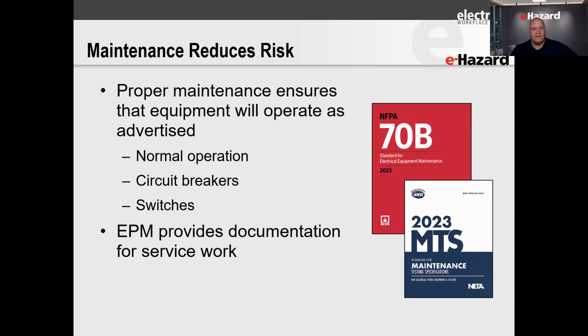Circuit breakers, we base everything in 70E on, when we get to arc flash. Arc flash is about how much current's going to be during the arc and how long it's going to be allowed to persist. So circuit breaker maintenance is huge, because if we don't maintain our breakers, do proper lubrication, test them, make sure they trip at the right setting and are set correctly, we've missed something in the engineering study.